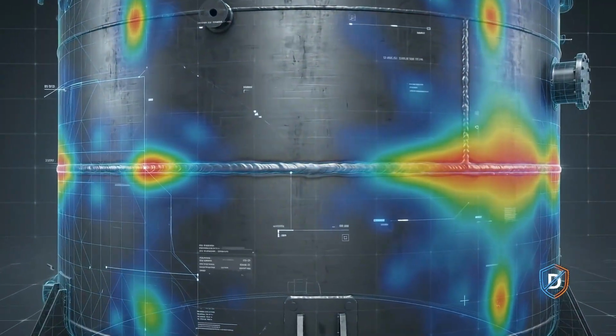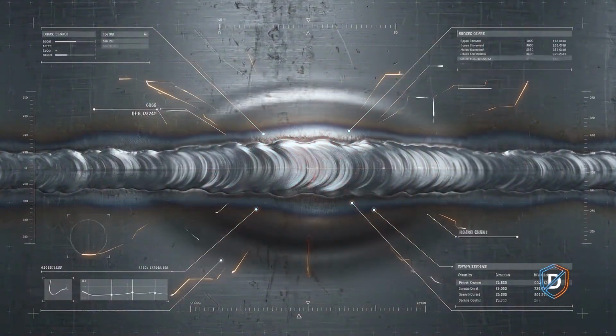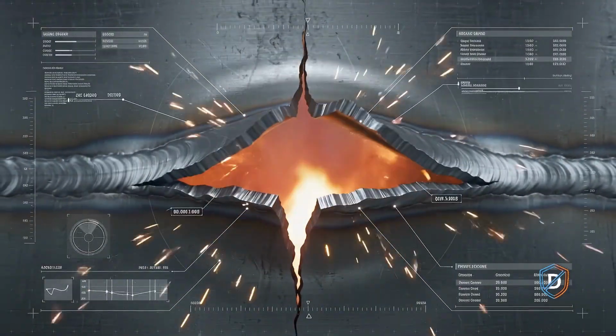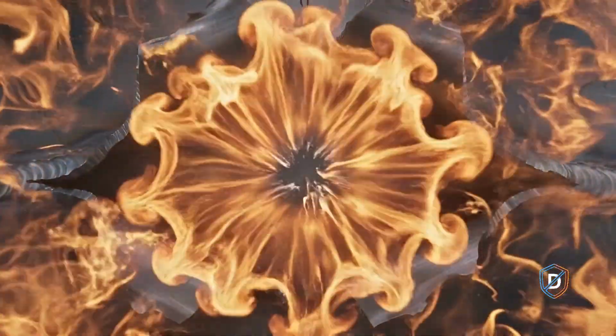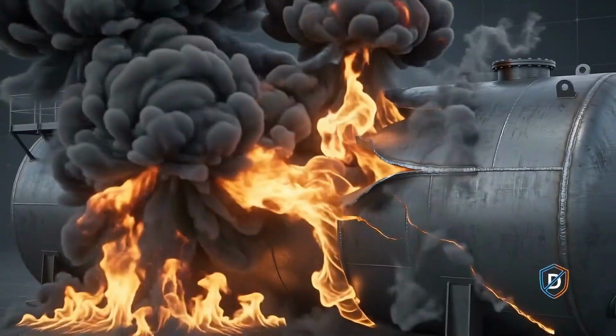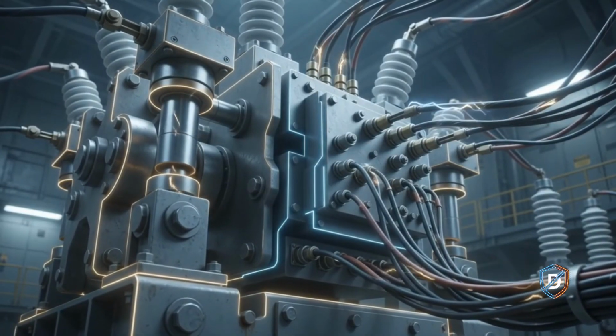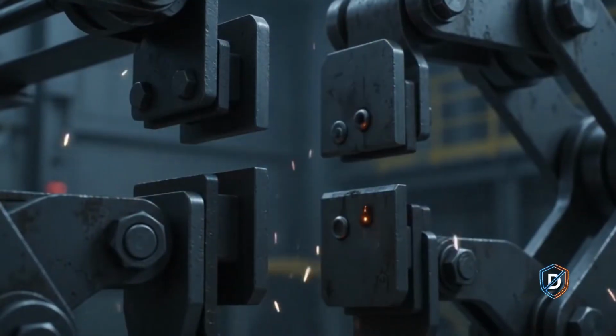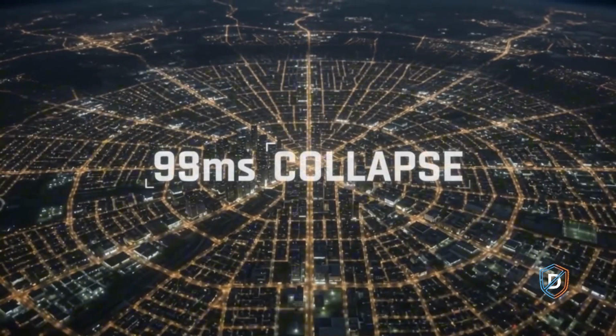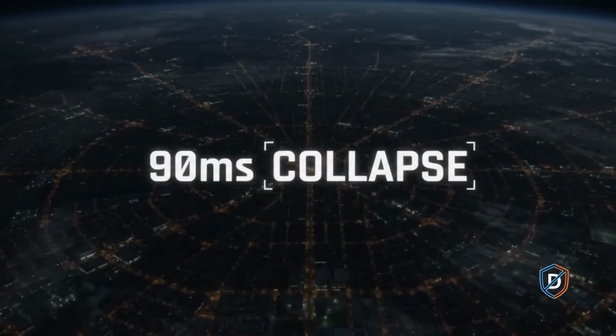Superheated copper bakes surrounding transformer fluid, generating explosive hydrogen gas trapped inside a sealed steel vessel. When internal pressure breaches structural limits, the outer steel seam tears open, exposing superheated oil to open air. A single core failure triggers automated breakers, dropping a multi-state power grid off the line in under 90 milliseconds.